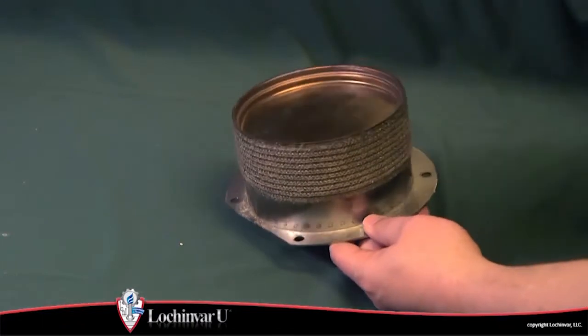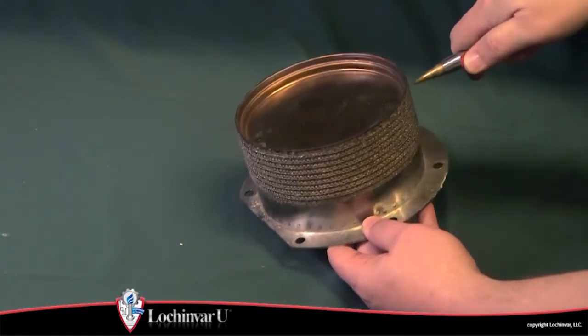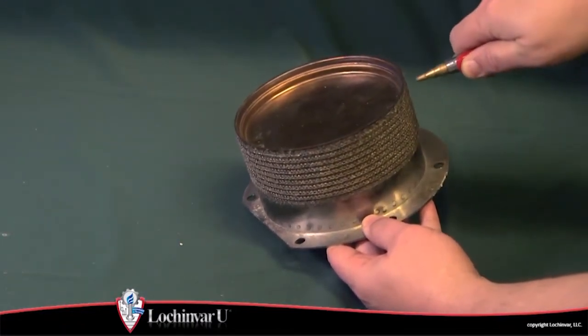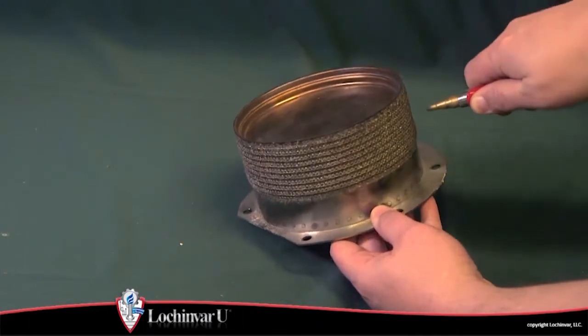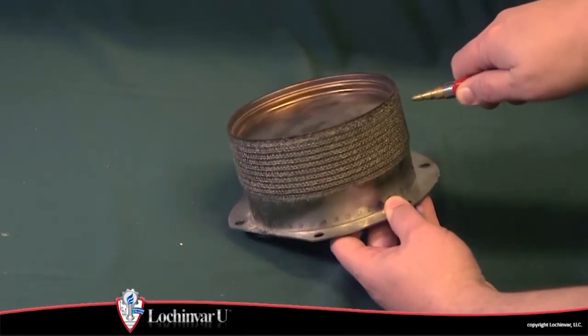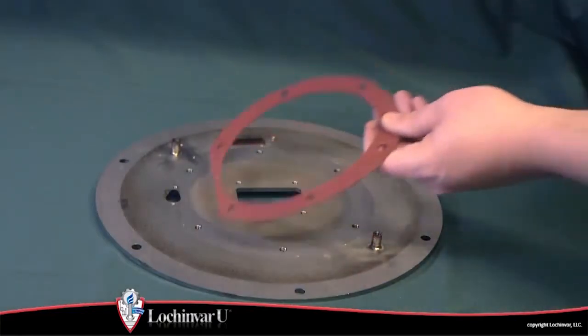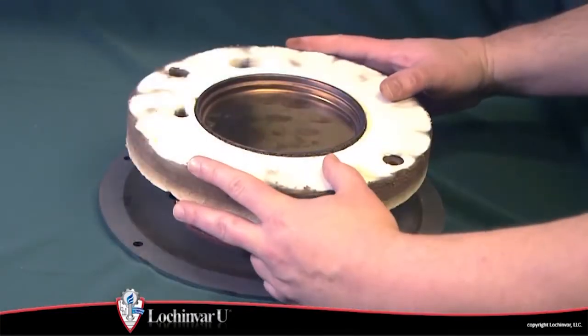If no damage is observed, slowly clean the burner by using compressed air to blow through the surface of the burner. This process may take some time depending on the level of contamination. Now reattach the burner to the heat exchanger top plate and reinstall the insulating refractory on the heat exchanger top plate.